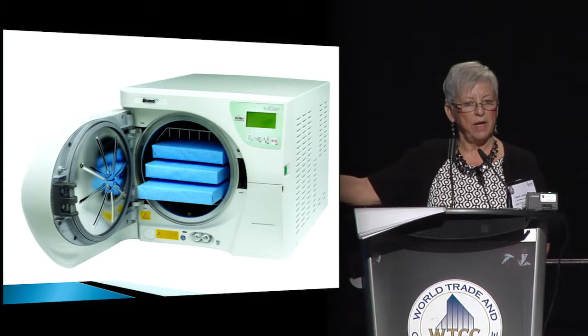So there are different ones out there. There's some really old ones out there. And the thing with the tabletops, again, is the printing capability, or you need to be able to look at that record, because often when you start a sterilizer, you will start it, go ahead and do something else and come back. But you need to review those parameters around what actually happened within that sterilizer.